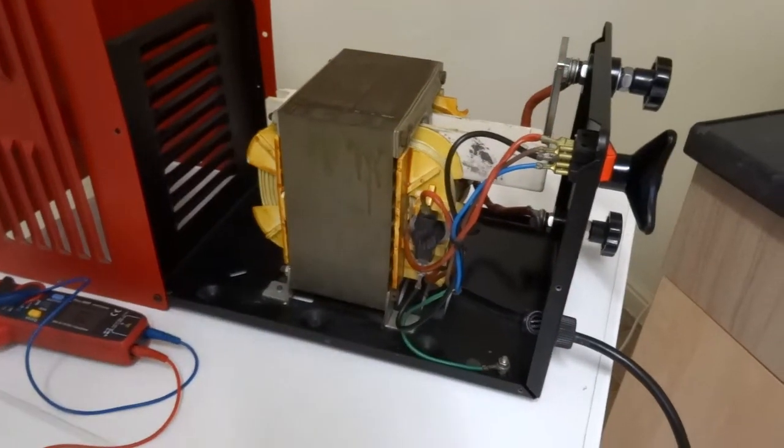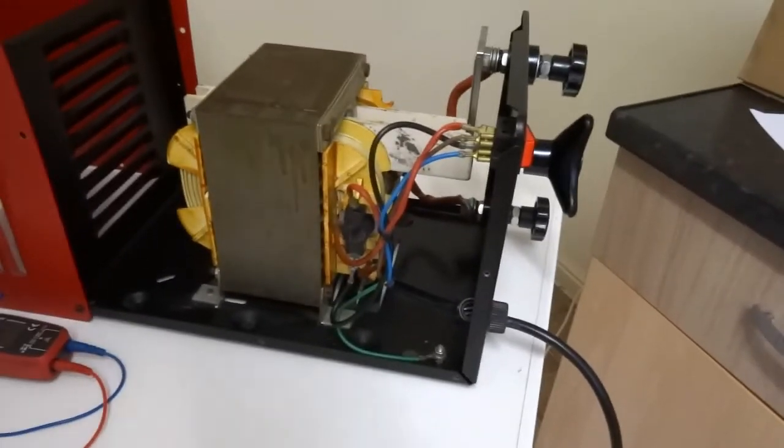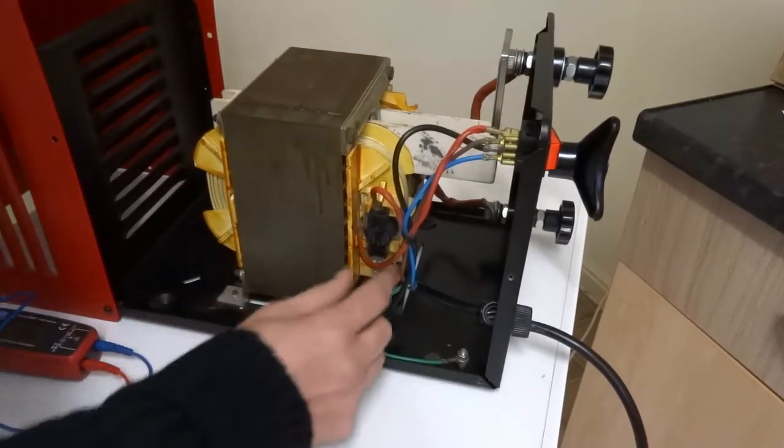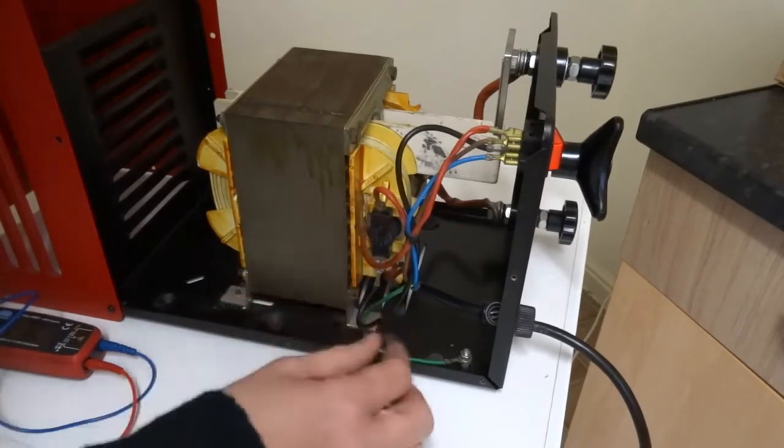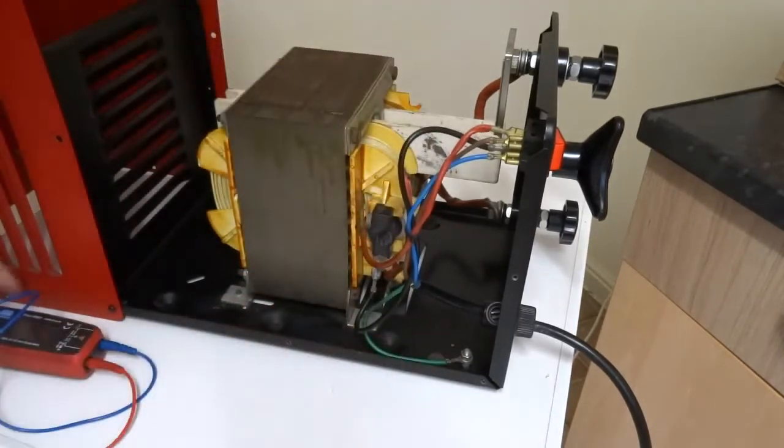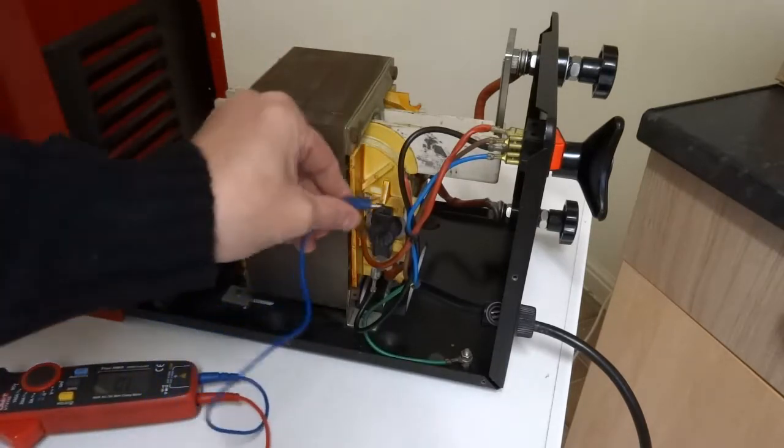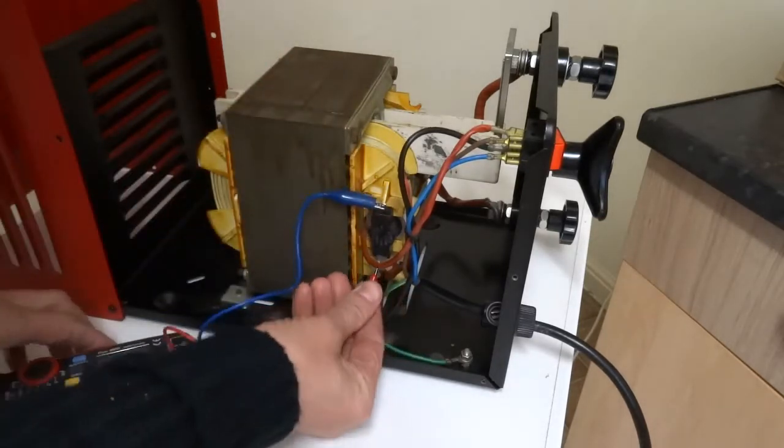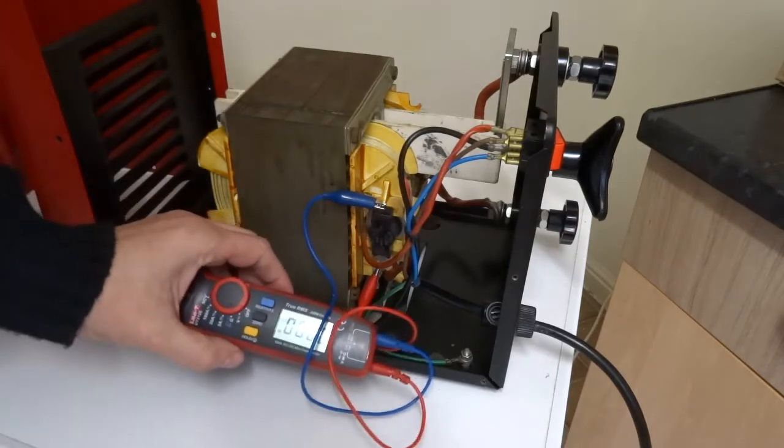All right, the next thing to check on these is the thermal cutout, which is there. So I'm going to pull both these cables off and just do the same again, test for continuity between them. As you can read, really low ohms reading.